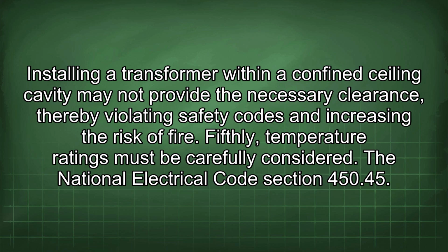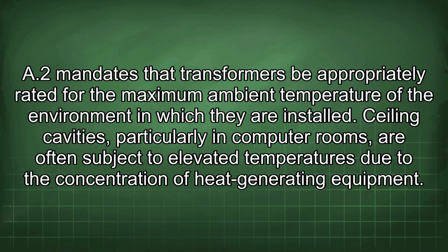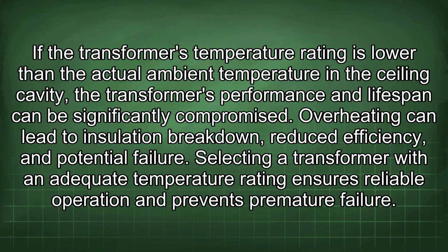Fifthly, temperature ratings must be carefully considered. The National Electrical Code Section 450.45(a) mandates that transformers be appropriately rated for the maximum ambient temperature of the environment in which they are installed. Ceiling cavities, particularly in computer rooms, are often subject to elevated temperatures due to the concentration of heat-generating equipment. If the transformer's temperature rating is lower than the actual ambient temperature in the ceiling cavity, the transformer's performance and lifespan can be significantly compromised. Overheating can lead to insulation breakdown, reduced efficiency, and potential failure. Selecting a transformer with an adequate temperature rating ensures reliable operation and prevents premature failure.